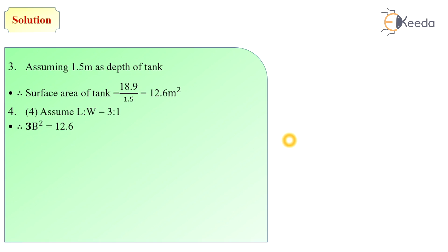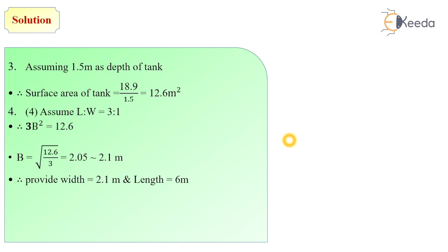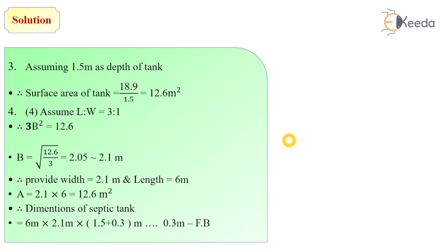Area equals length into width, and since length equals 3w, we get 3b squared equals 12.6. From that equation, width equals 2.1 meters. We provide width equal to 2.1 meters and length equal to 3 times its width, which equals 6 meters. The actual area of the septic tank is 2.1 into 6 equals 12.6 square meters. So the dimensions of the septic tank are 6 m × 2.1 m × 1.5 m, plus a freeboard of 0.3 meters.